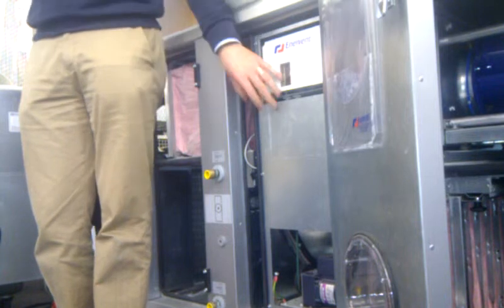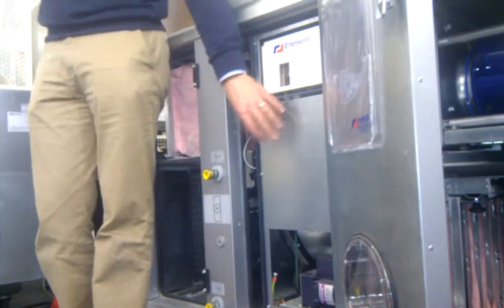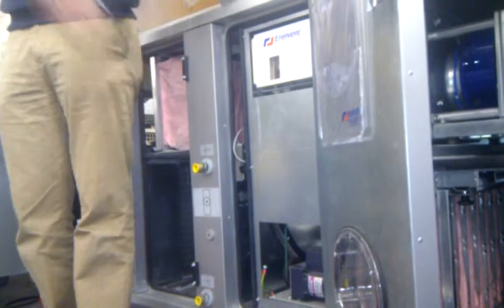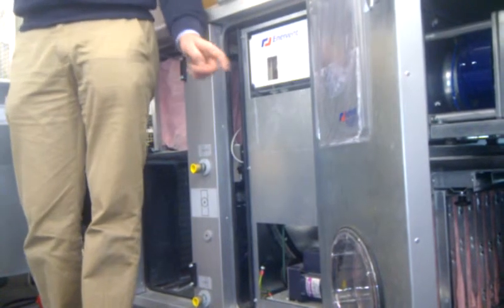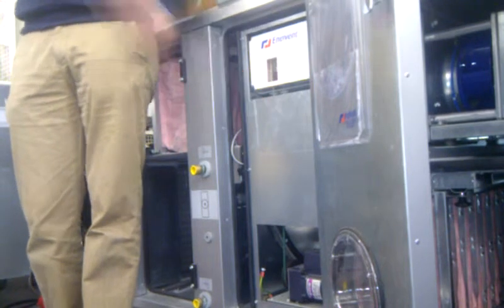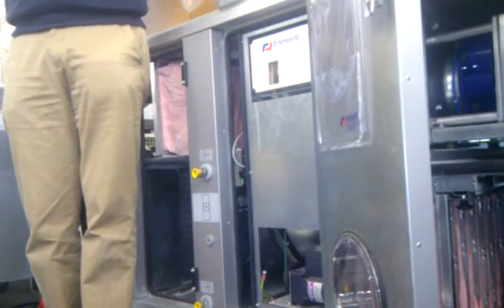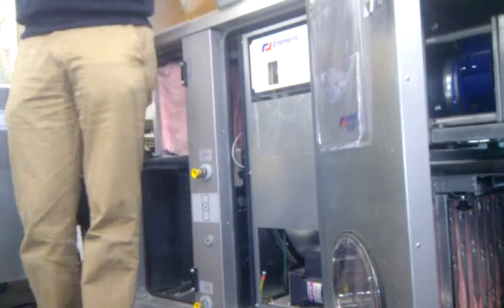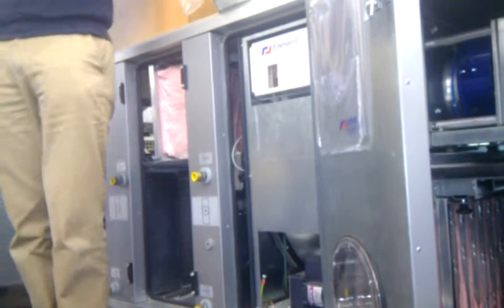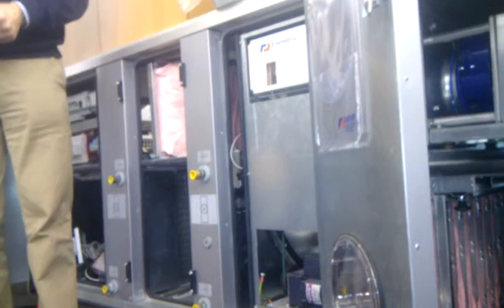And what they say is the 0 to 100%, as it requires it, speeds up or slows down this wheel. That's the same as increasing the amount of heat being recovered to control the temperature. And then once this is flat out and it's still not meeting the temperature you need, it starts opening the valve next. So it always recovers the heat before it starts using the boiler temperature, which is only common sense. But you'd be amazed the amount of people who don't apply common sense when they're doing things.